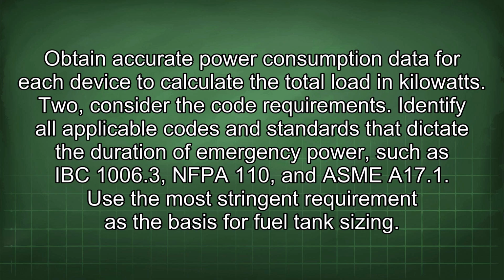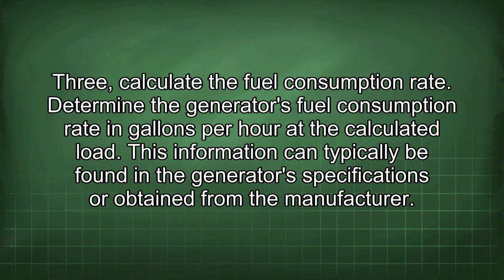2. Consider the code requirements. Identify all applicable codes and standards that dictate the duration of emergency power, such as IBC 1006.3, NFPA 110, and ASME A17.1. Use the most stringent requirement as the basis for fuel tank sizing. 3. Calculate the fuel consumption rate. Determine the generator's fuel consumption rate in gallons per hour at the calculated load. This information can typically be found in the generator specifications or obtained from the manufacturer.